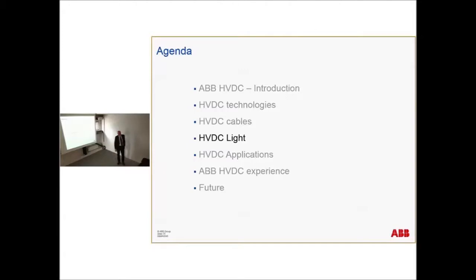Question. Yes. What is the expected life length of such cable installations? I know it's a bit different. We say once the cable is correctly installed and buried, the failure rate is almost zero, because it is tested electrically when it is delivered from the factory, and you also do a new electrical test when it's installed. So then it's only subject to, I would say, mechanical forces during the lifetime. It can be current if it's a free cable, or bendings and things, vibrations, etc.